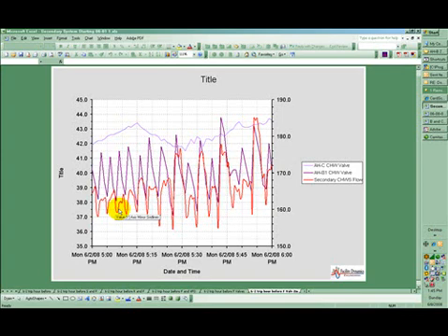So the valve is very significant in its ability to impact the flow on the secondary. And so I guess what I'm suggesting is that we really need to look into stabilizing that flow. And to do that, I think the trick might actually be getting the air handling unit B control valve to be stable. It's not out of the question the flow is driving the valve crazy, but I think it might be the other way. And so what I'm suggesting is, as a real easy test, that we simply take a hold of this air handling unit B valve command and lock it down to something like 39%. Now, I picked 39% because if you look at what's been going on, like for that whole week.